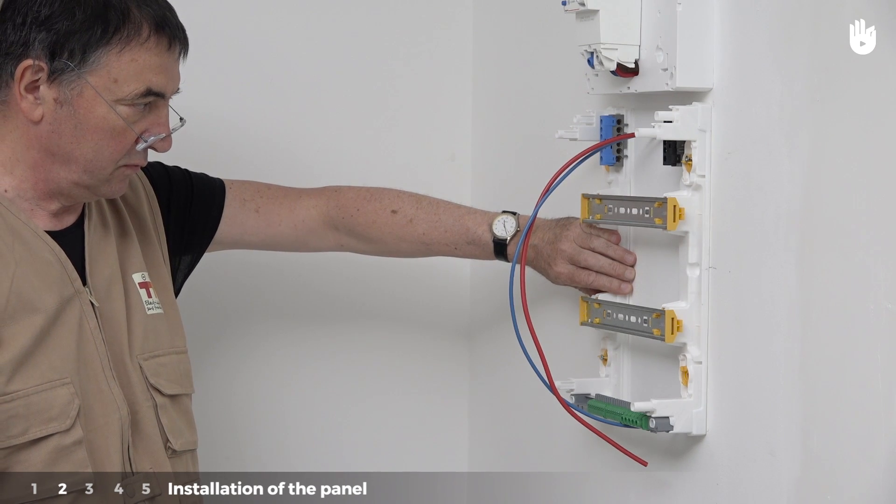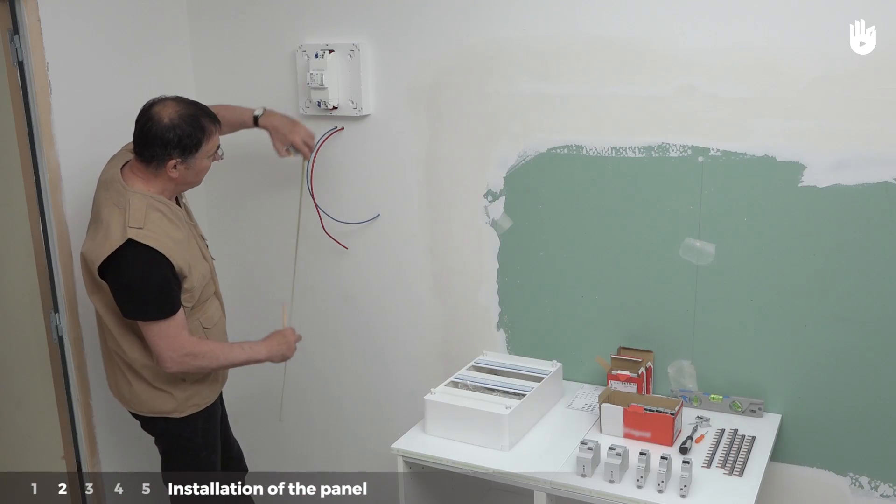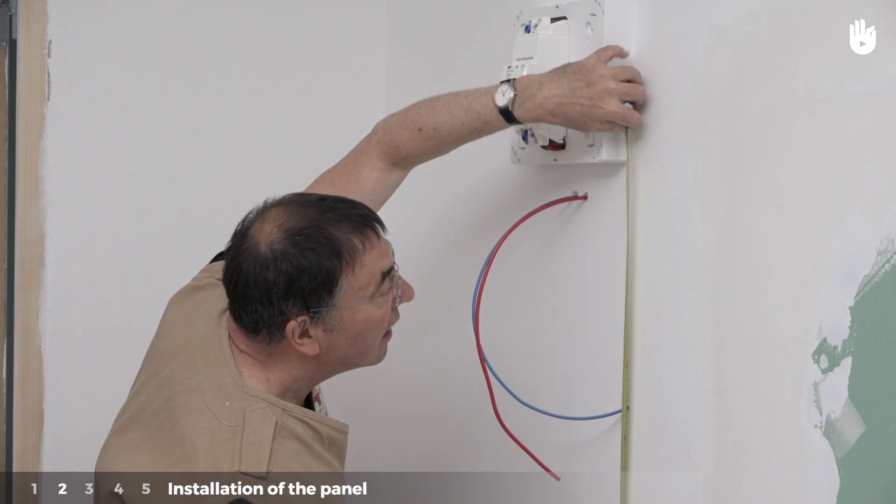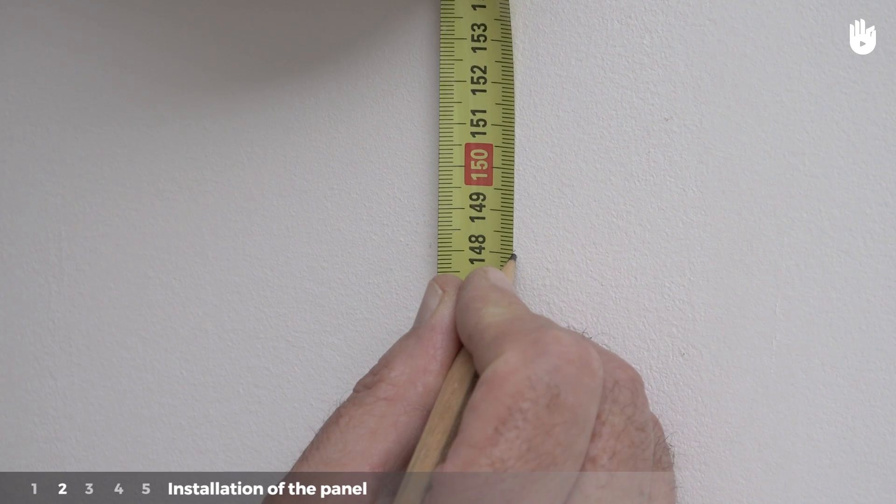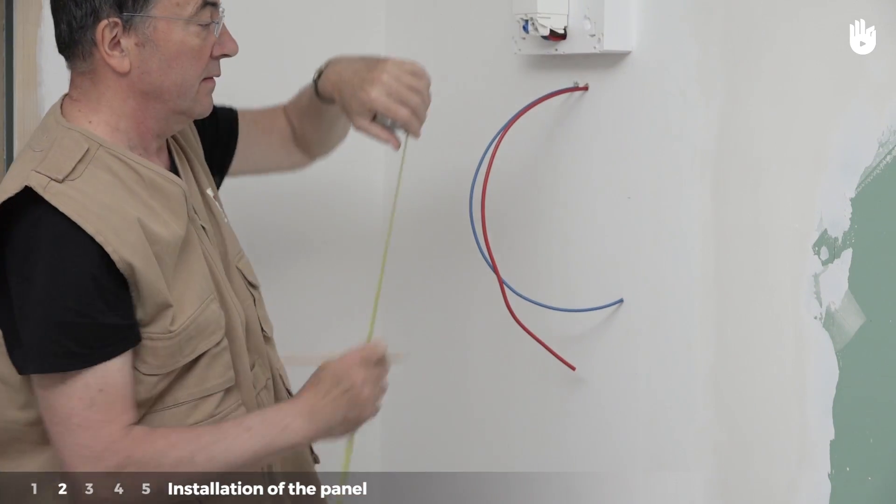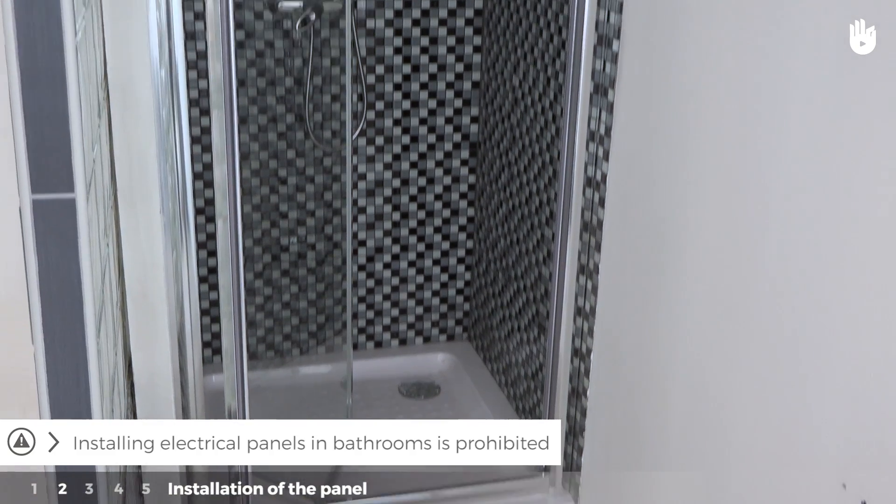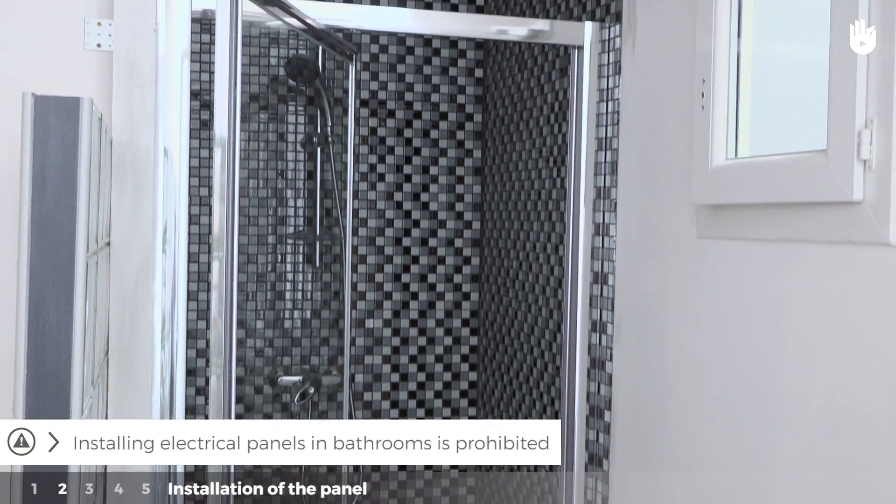Step 2. Installation of the panel. Be careful! Installing an electrical panel must be done in compliance with strict regulations. It must be installed inside the residence at a height of between 1 to 1.8 meters above floor level and must be located close to the branch circuit breaker. Please note that installing electrical panels in bathrooms is prohibited.